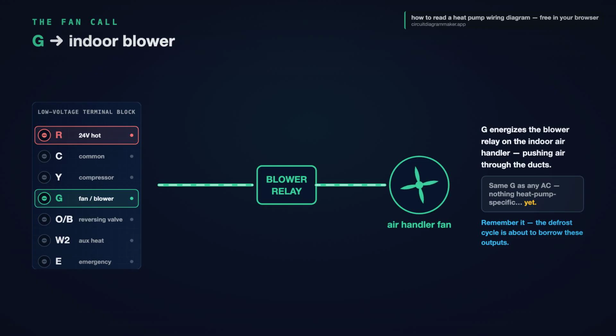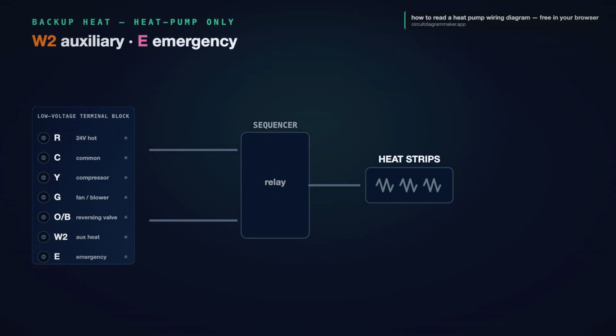Nothing heat pump specific here. It is the same G you would find on an air conditioner. But you'll want to spot it, because in a moment the defrost cycle is going to borrow control of these same outputs. Here is another heat pump only section, auxiliary and emergency heat.